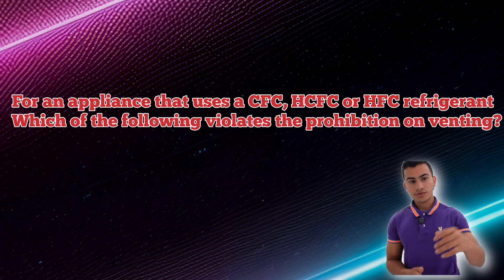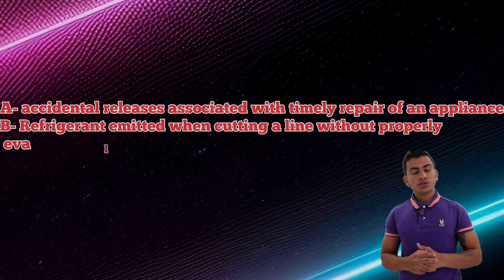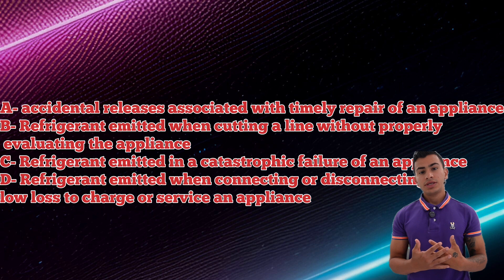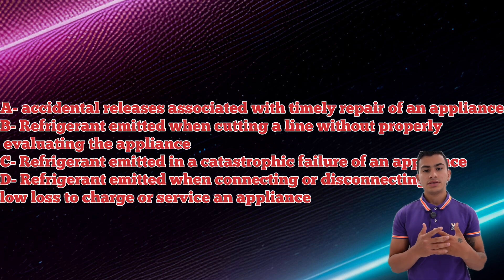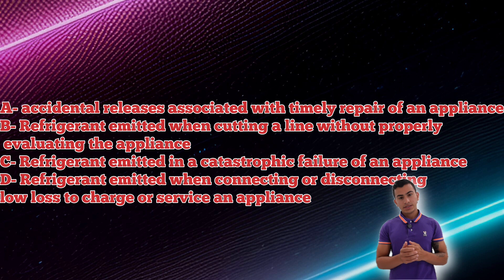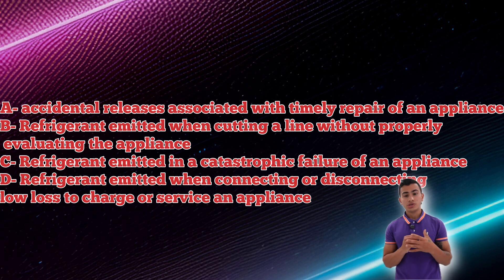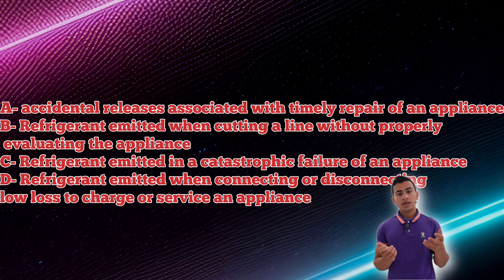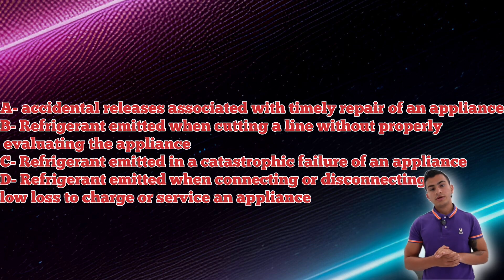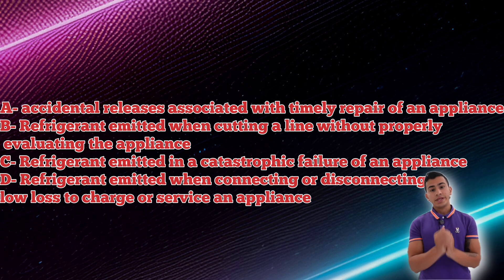For appliances that use CFC, HCFC, and HFC refrigerant, which of the following violates the prohibition on venting? An accidental release — no, it says accidental, meaning you couldn't control it. Refrigerant emitted when connecting or disconnecting hoses with low-loss fittings — no, low-loss fittings are there for a reason and the small amount released is called de minimis. The answer is refrigerant emitted when cutting a line without properly evacuating the system — it is your fault because you did not evacuate the system.